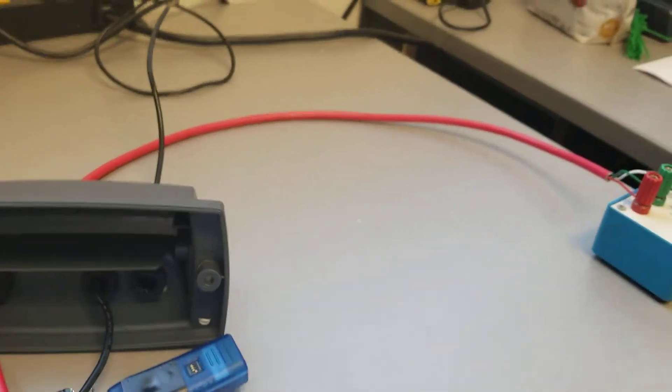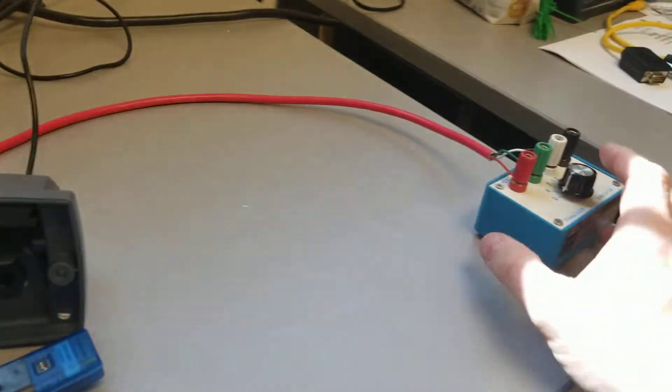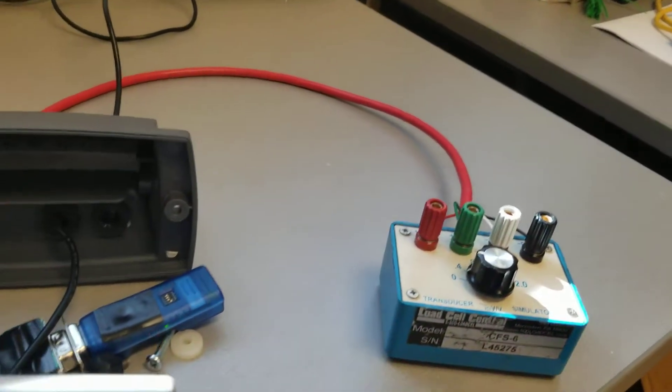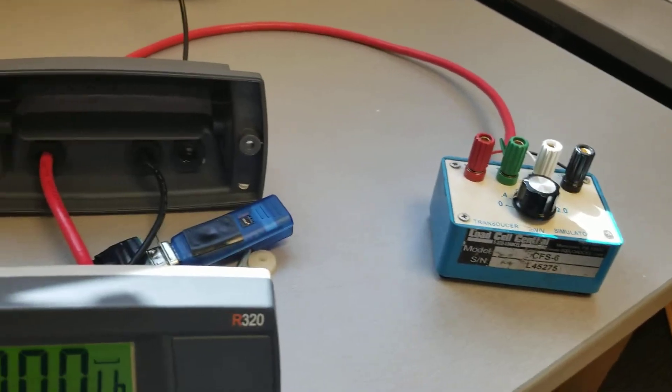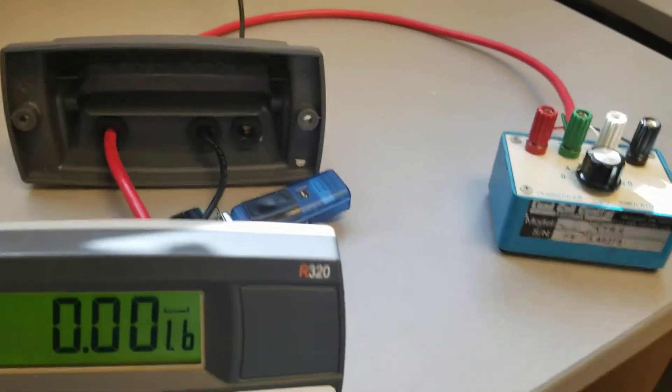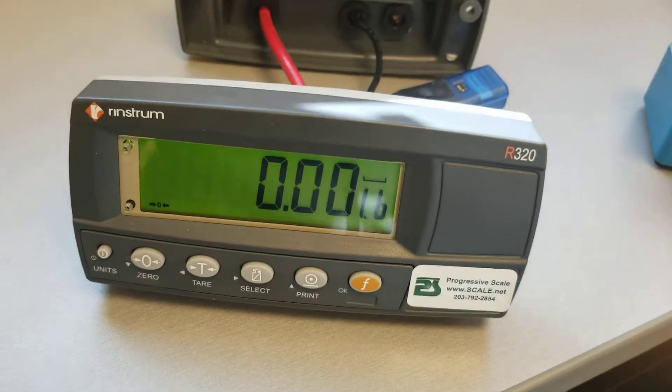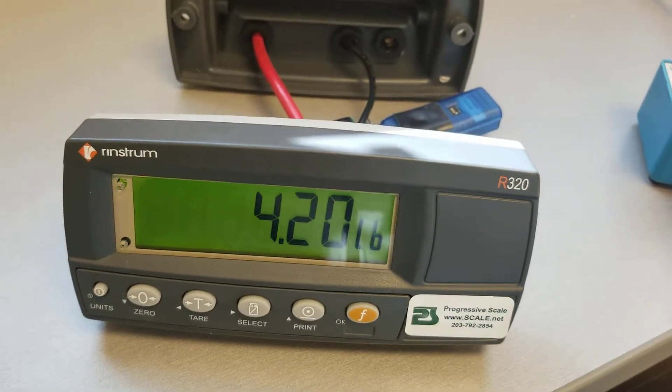In this case our weighing platform, I'm using a load cell simulator that simulates weight. So all I got to do is change the weight and weight jumps around.